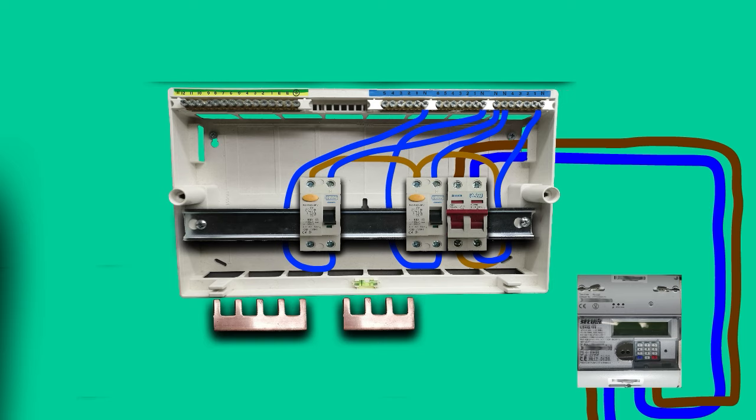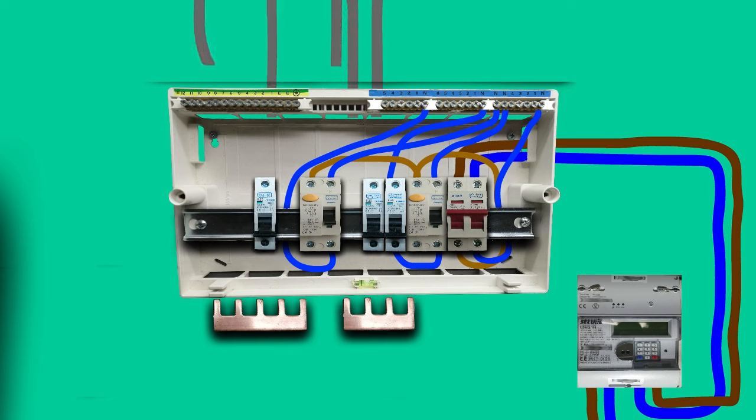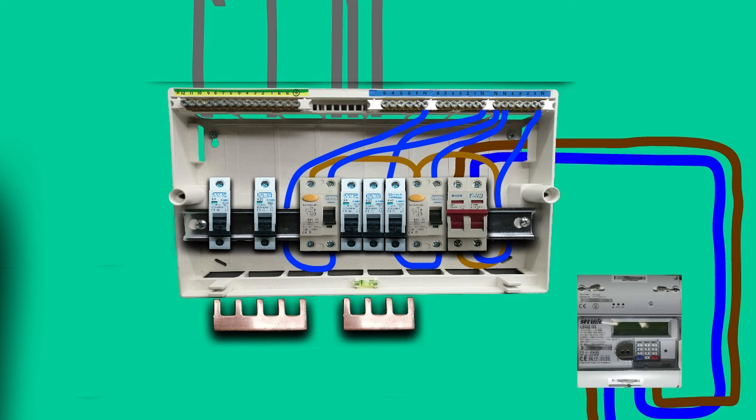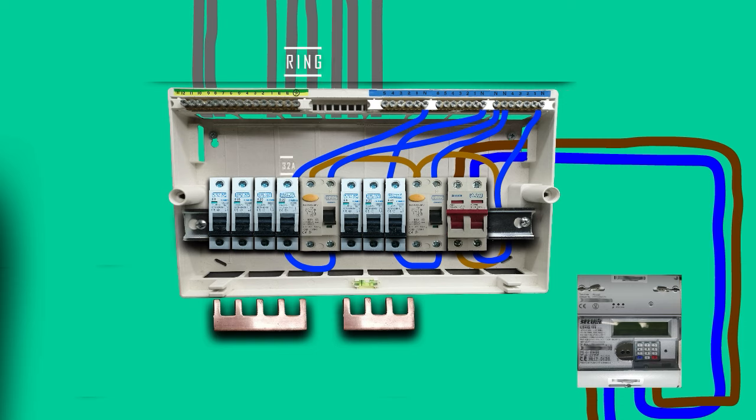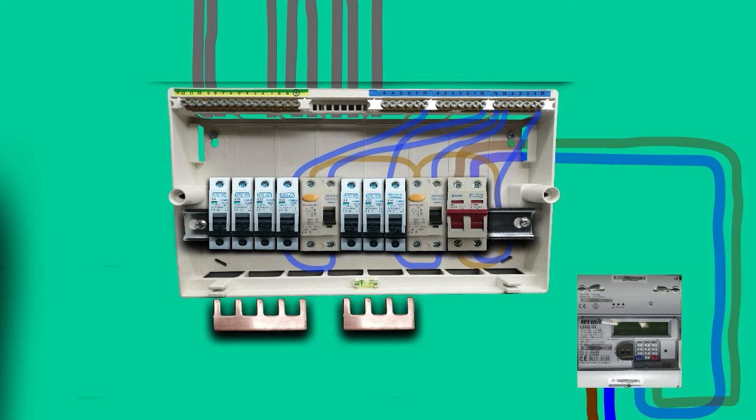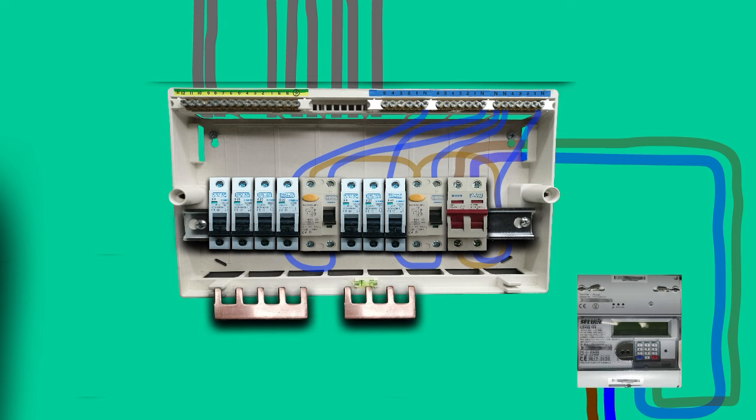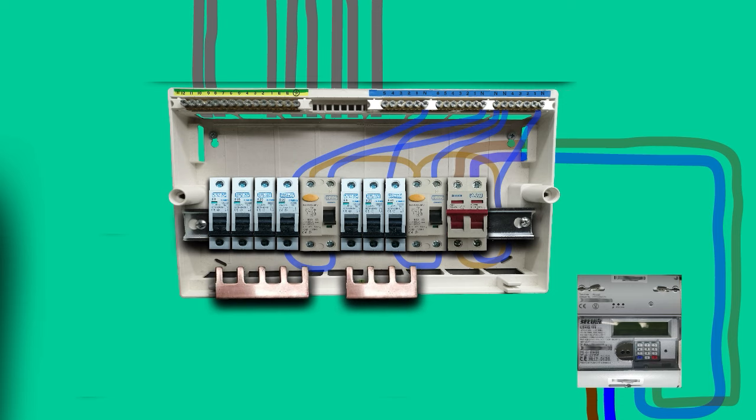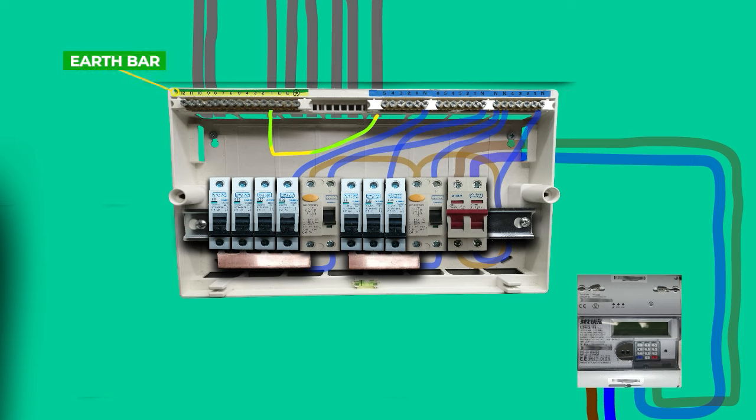Now let's bring back our cables and MCBs. So we need to wire one cable from each circuit to one MCB as well as to the neutral and earth bars. The only exception here is the ring final circuit where we've got two cables and one MCB. So we have all cables and MCBs in place and we know which cable is from which circuit. Let's say all the cables are in order from right to left to match the MCBs from right to left. So let's do the earthing wires first. The earthing wire from the first cable goes to terminal 1 on the earthing bar. From cable 2 to terminal 2 and so on. And only the two earthing wires from both ring cables go to one terminal instead of two.